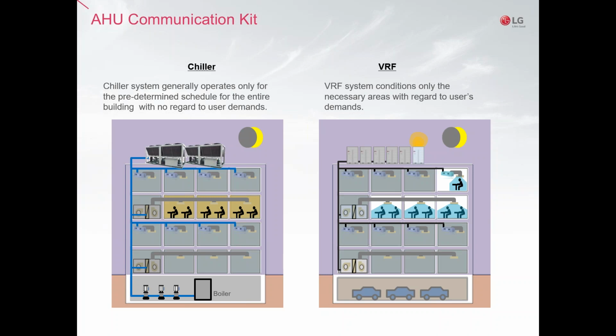In the picture on the left, you have a very heavy 20-year-old chiller on the roof with water piping, probably constant volume, running all the time to give service even to one small area of the building. You probably have old piping, old pumps, and very large boilers. These systems were very good and gave very good service during their time, but now after 20 years, their efficiency is very low. So one possibility, which is more attractive when you already have leaking pipes or the new chillers are heavier.